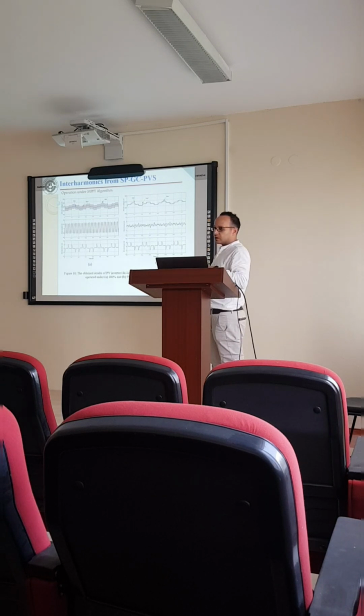For the operation under, for example, the perturb and observe control algorithm, as we can see, this is the full load operation, and this is the no load or low load operating condition, under 5% of the full power. As we can see, this is the DC perturbation.